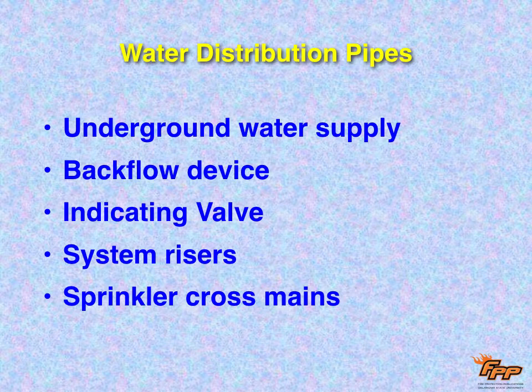So there has to be what is called a backflow device, and it has a clapper valve in it and other valves that stop water from going from the fire protection system back into the public water. We don't want to drink that stuff because over time it gets gross. It's smelly, it's black. If you've ever seen a sprinkler system turn on, it's black water that comes out. It's really gross. Lots of mold and that. So that backflow device is usually going to be an OS&Y, which is an indicating valve. We need to be able to tell from the street whether the fire sprinkler system is on or off.